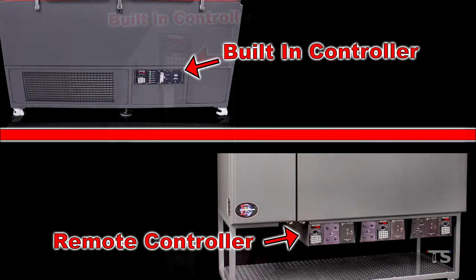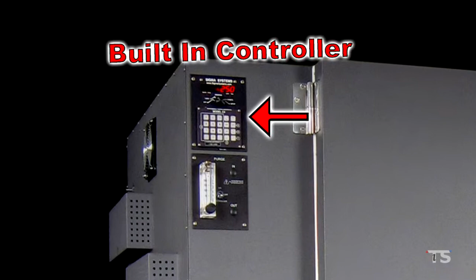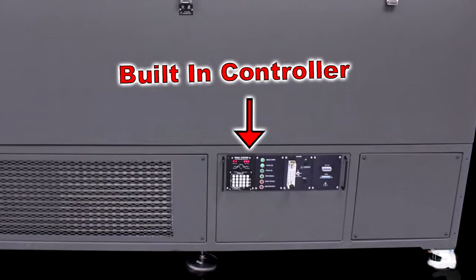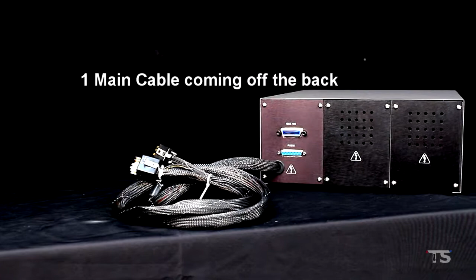Let's start by showing you the difference between a built-in controller and a remote controller. A built-in controller is built into the chamber's chassis. There are no cables or connections coming off of the controller; all of the connections are already made inside the chamber. A remote C4 controller has one main cable coming off the back.